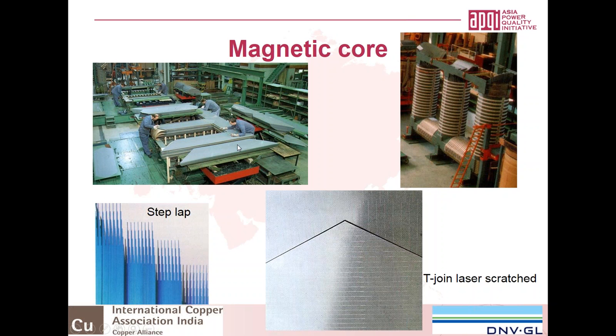If you look at the transformer sheets which are used, that's a kind of iron which they use, and you can use also, and that's the picture on the right side, a T-join laser scratched. To reduce the losses, it's necessary that you pick up the right connection of the flux going, the right density of the flux, and sometimes to make sure that the connections are very good within a transformer and you get less load, they make a kind of step-lap pattern. So you have a good overlap between all the sheets which you have. And also another way is looking at a laser scratch material, and that's what you see over here. You'll see some nice grooves going in the vertical direction and over here in the horizontal direction. That's just to guide the flux within the transformer to make sure that the losses are as low as possible within this transformer.